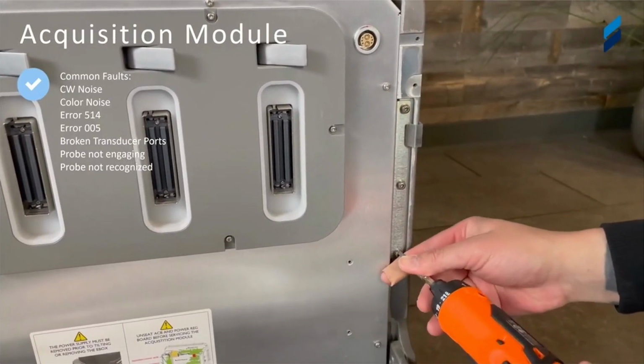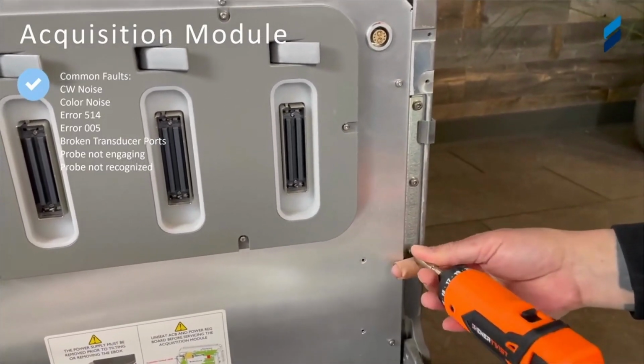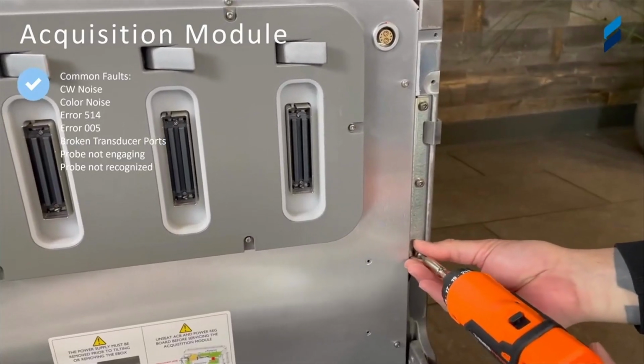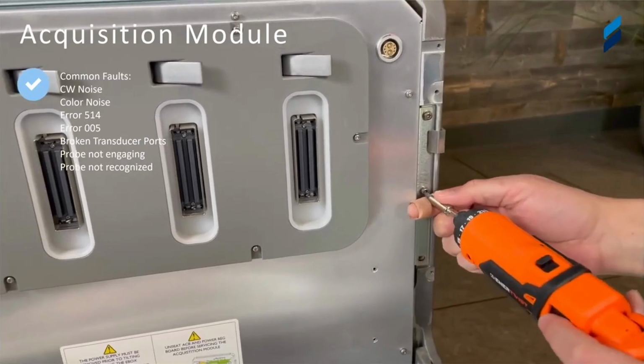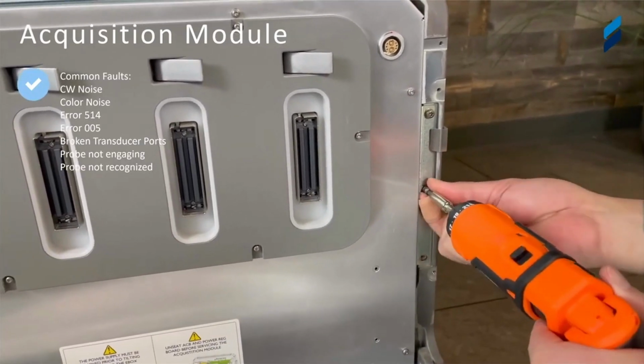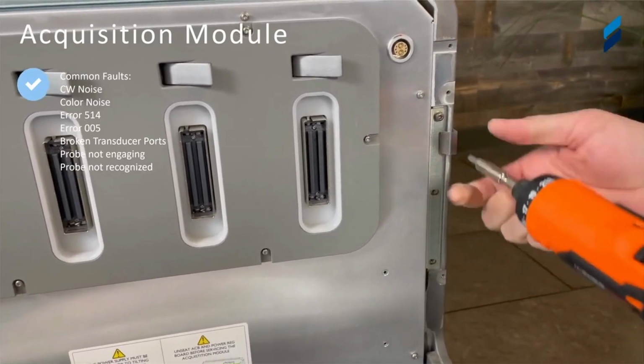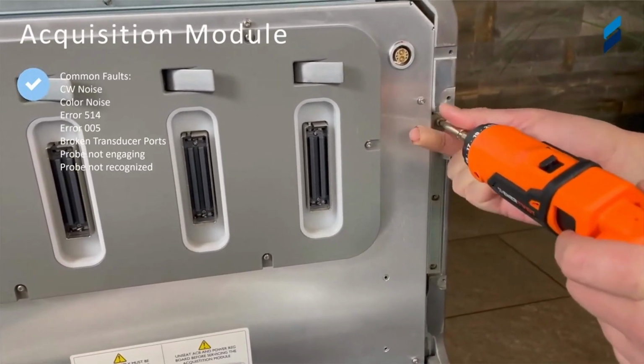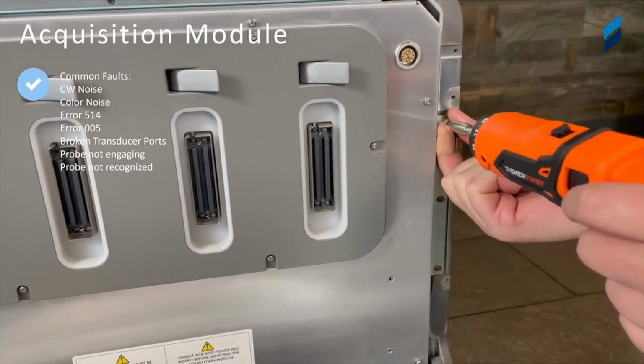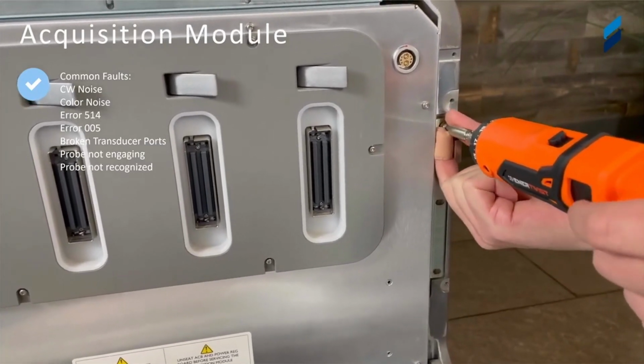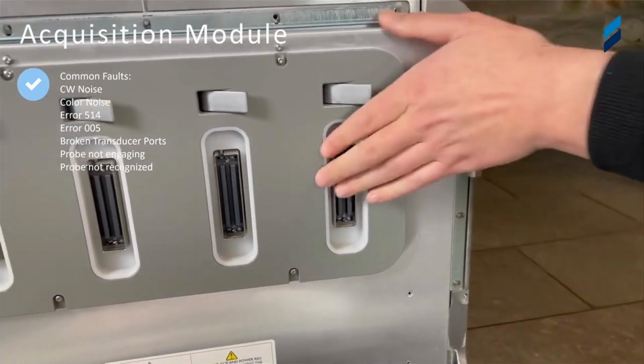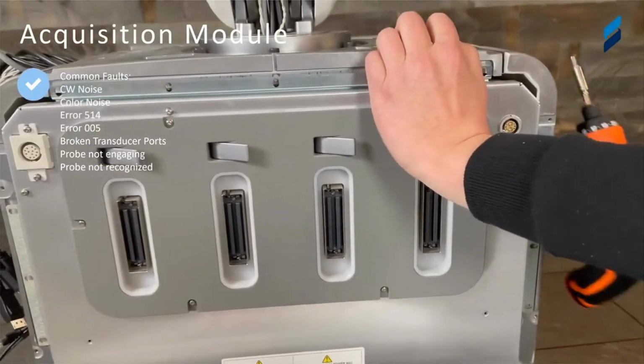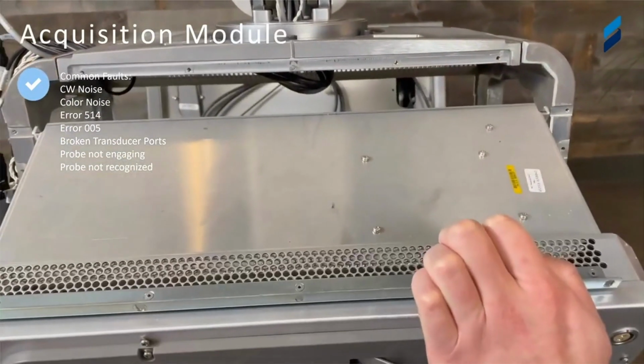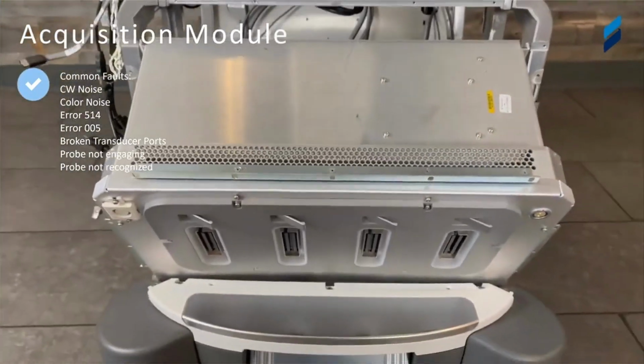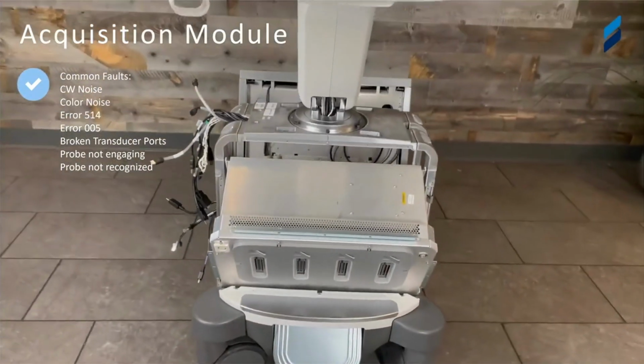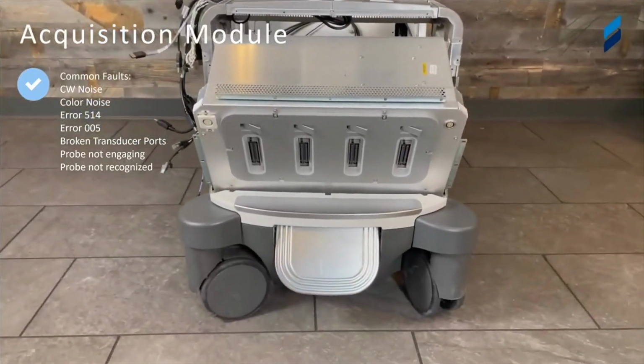And there's that right latch that will prevent the whole Ebox and acquisition module assembly from tilting forward. It's going to tilt forward with all the screws removed. That's what's going to hold it up, so there's no accidental tilting and unnecessary impact to the assembly. So now that we have all the screws removed, we're going to pull out to the right on that tab and let it fall forward.